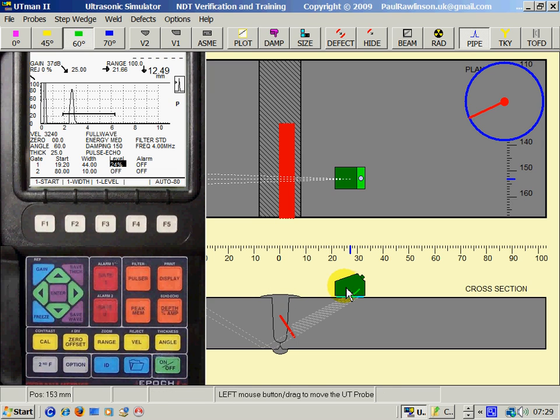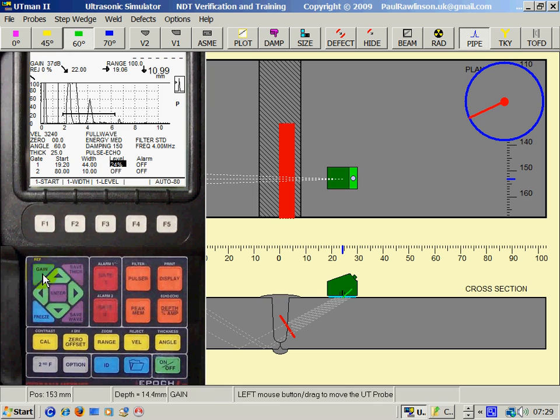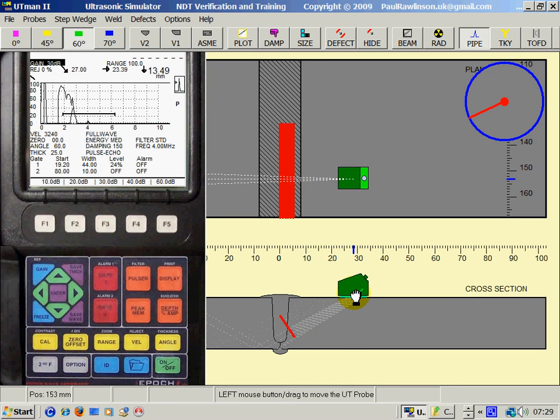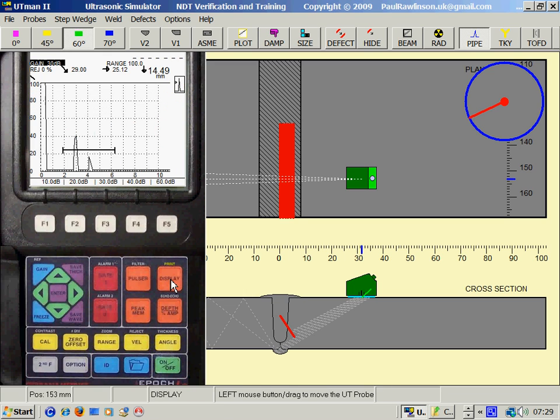Peak memory will record the highest echo. I'll reduce the amplitude there. So you can see it's recording the echo position here. A P is displayed here, letter P, to show that peak memory is on. Display will change the display.